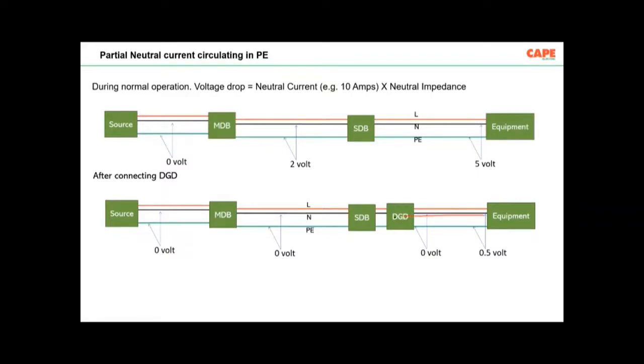up to this place. Then partial neutral current will flow through the neutral conductor, and balanced current will flow through the earth conductor. This neutral current which is flowing through the earth conductor is a kind of circulating current. Imagine your neutral current is 10 ampere, but after connecting this particular device, about 5 ampere current flows through your earth conductor, but our maximum allowed current is, let us say, for example, 10 milliampere.